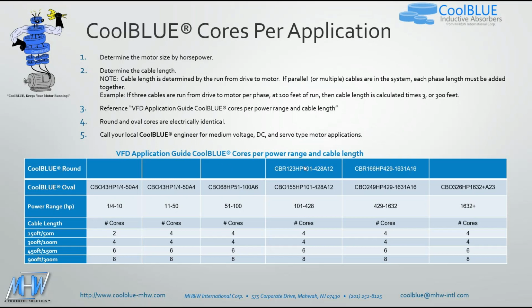As you see on the screen, this is basically the application guide. Right here is the horsepower range of your motors. Here are your cable lengths in the left column. So if you have a 75 horsepower motor, you're in this column. If you have 150 feet of cable, you're going to use 4 CoolBLUE cores. And here's the part number for those particular cores. It's very important that you use the cores that are called out. You don't want to use a smaller core, and you really don't want to use a larger core if you don't have to. It costs more money, and it doesn't make sense.